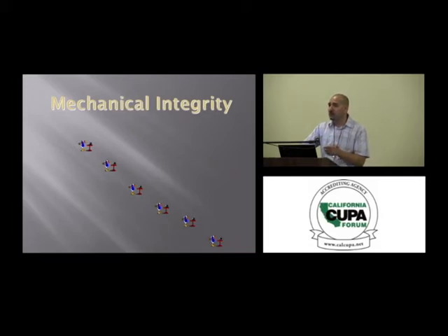When you're out there looking around, just to give you an idea, if you don't know what they look like, we like to use Hansen relief valves, and they have a green tag. The installation date tag is green. Every time I see that, I know that it's a reduced capacity. It's been sized accordingly. So it does make a difference, like Michael said.